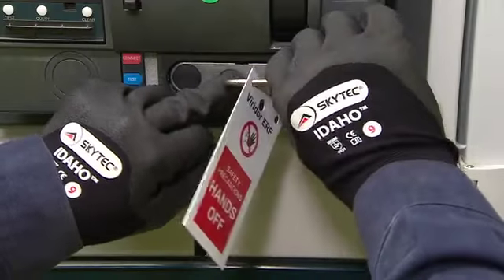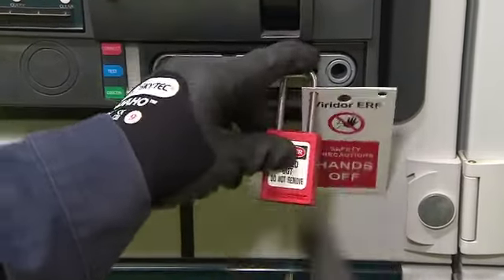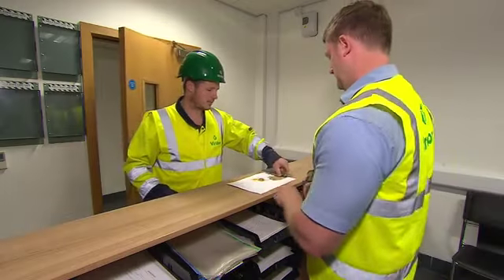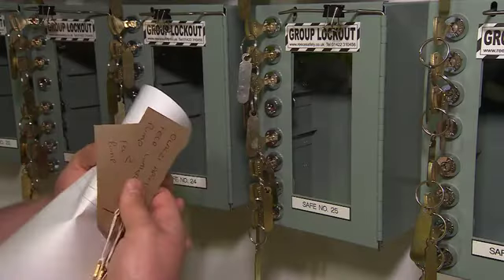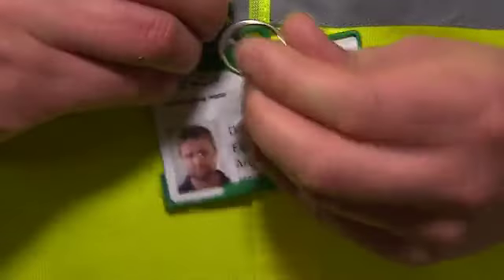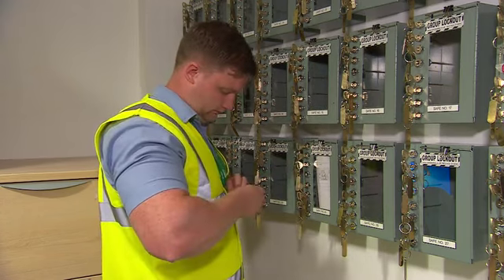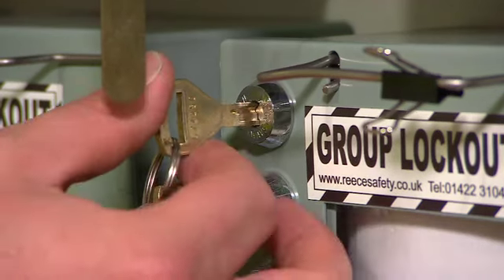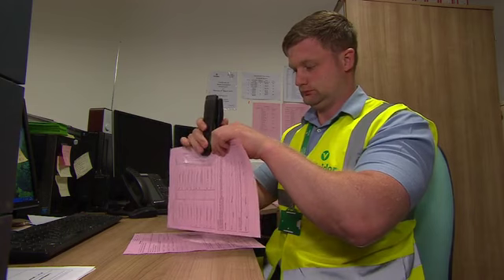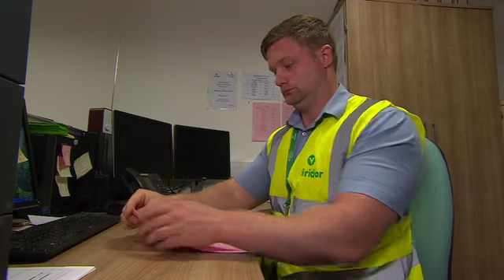Any safety precautions in place on the facility will have a red padlock and caution notice in place. These points of isolation must not be tampered with in any way. When all the precautions have been put in place, the keys are secured by the senior authorised person in a key safe using their control key. A key safe key is then removed from the key safe and attached to the permit to work, and will not be released until all the work has been completed. If there is no key attached to the permit for work, do not accept the safety document.